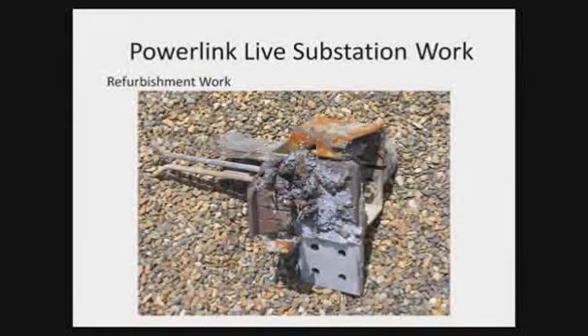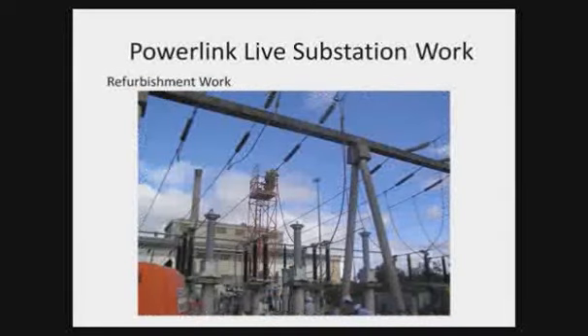This is just a slide that was part of this particular presentation. So this particular isolator, that's what happened to it. There was a fault on it, and our job was to shunt out, bridge out effectively a whole bay there, so that contractors come in and replace the isolator. So if you look, you'll see two phases already bridged out, third phase in the process of being bridged out.